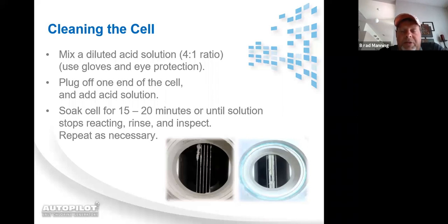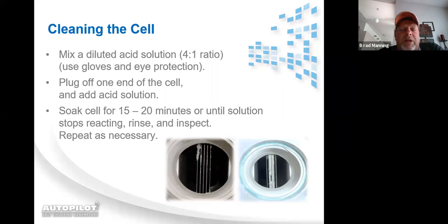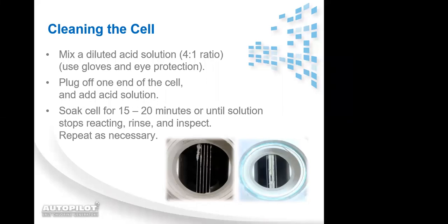So by plugging the simulator in, you would wait the 1.5 minutes for it to acclimate itself to the simulator, and then you would do a test and see what it's reading the simulator at. Okay, and you mentioned the part number earlier for that simulator. Yes, the part number for that simulator is a 986-ST. Okay, and that simulator is just a very simple diagnostic tool. And if you want one of those, just contact your sales rep and they can arrange to get it for you.